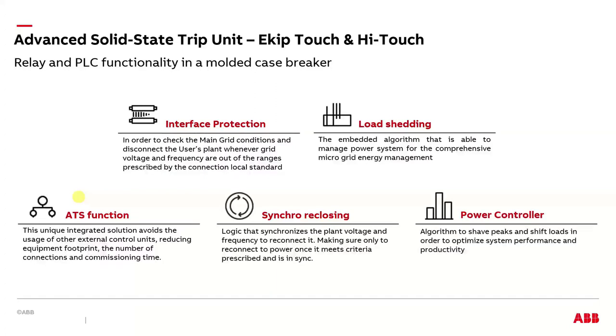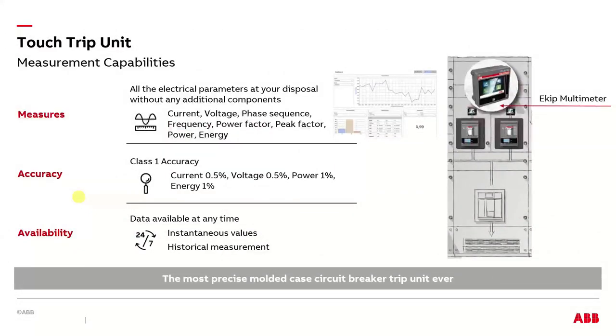Power controllers, so we can do peak shaving with generators or time of day control. And all these breakers can be remotely opened and closed if you get the accessory for them. This is what we call the touch trip unit for a T-Max. It's got enhanced metering capability. The original solid state trip units were kind of poor in their ability to meter. We had metering functions built into them, but their accuracy was about 5% at best. These breakers all use the newer Rogowski coil technology, so you can get a pretty high accuracy class just from the breaker's trip unit alone. So, for example, you can do class 1, 0.5% current, 0.5% voltage, 1% power and energy, which is a pretty good jump from where it used to be.